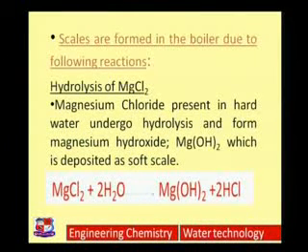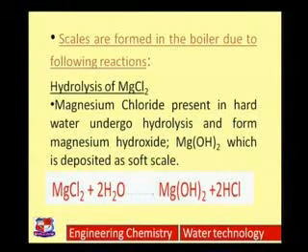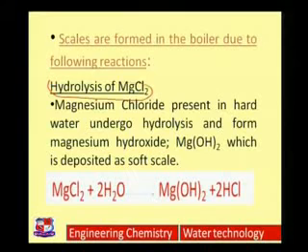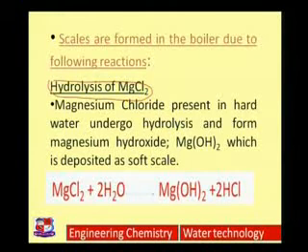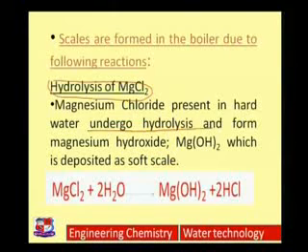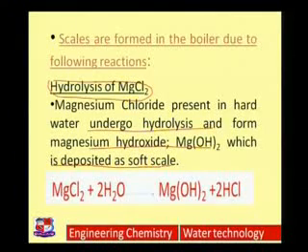Scales are formed in the boiler due to particular reactions. The first reaction is hydrolysis of magnesium chloride. Hydrolysis means cleavage by means of water — 'hydro' means water, 'lysis' means cleavage. The hardness-causing salt magnesium chloride present in hard water undergoes hydrolysis to form magnesium hydroxide, Mg(OH)2, which is deposited as a soft scale.